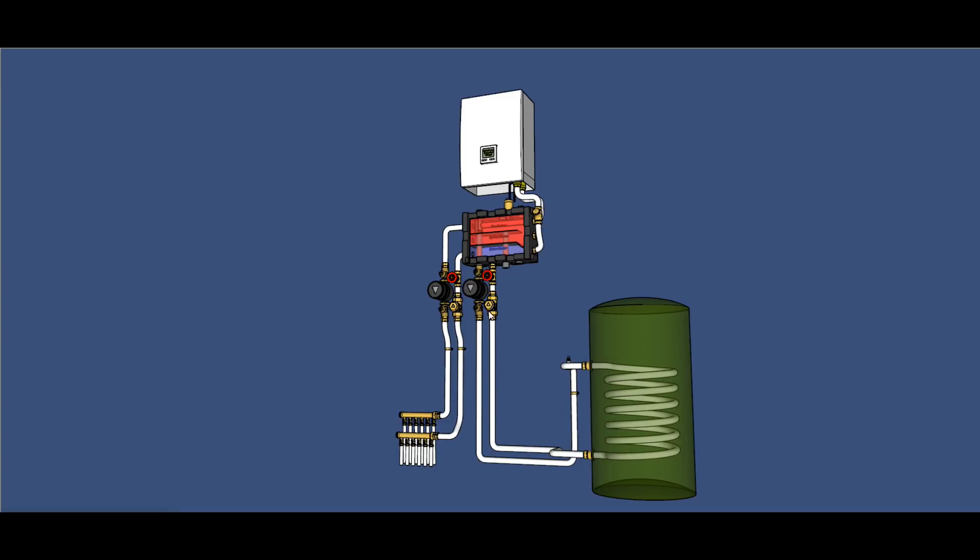In this example we show a non-return valve fitted here on the return port into the manifold. That's because the pipe drops down, goes across and rises back up - in other words it forms a heat trap.